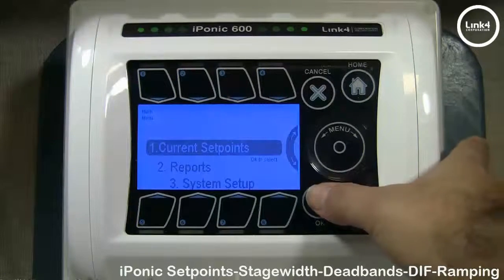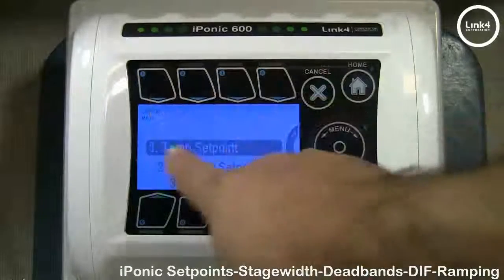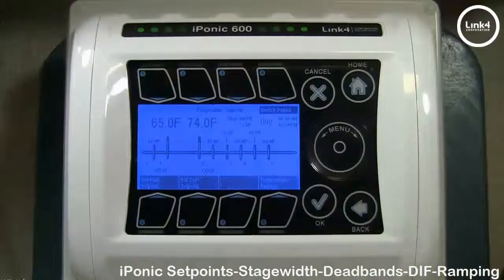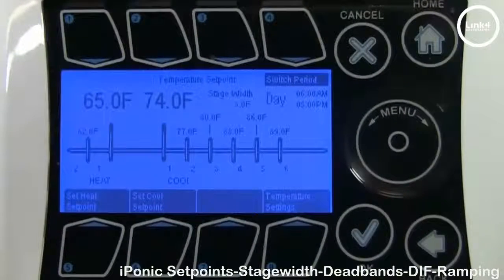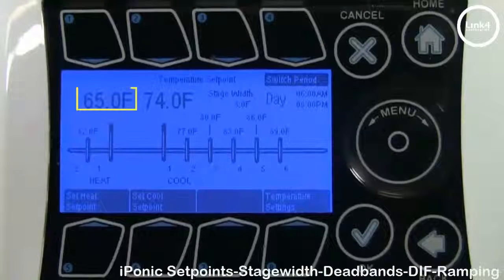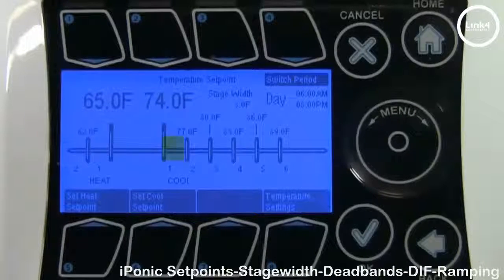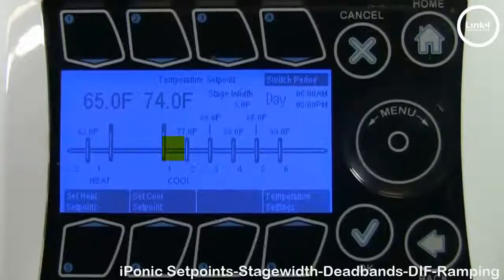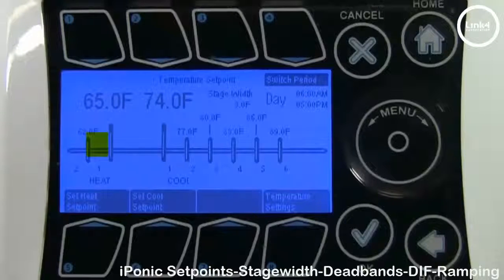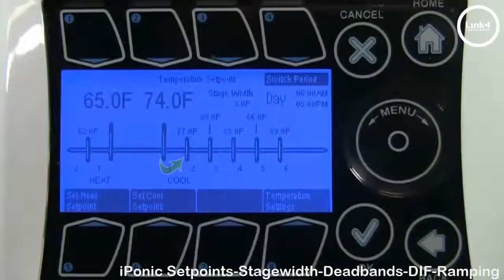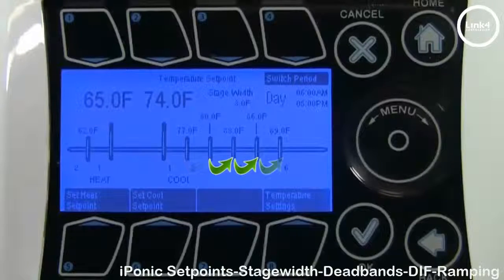To set up set points, from the home screen hit enter menu, go to current set points, and then go to number one temp set points. In the temp set point screen you have two large numerical values: the heat set point and the cool set point. If temp rises above the cool set point, cool stages engage. If temp falls below the heat set point, heat stages engage. The stage width or stage separation is the number of degrees between cooling and heating stages.